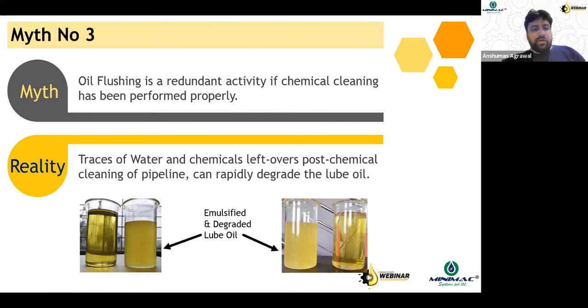Now, if you do not perform flushing, there would be traces of water and these chemicals, which would be sitting on the internals of your entire system. And when you actually fill up the oil, charge the oil into your system, and you start it, these chemicals will start mixing up with your oil and they would rapidly degrade it.